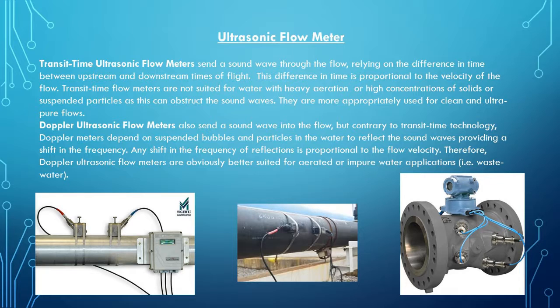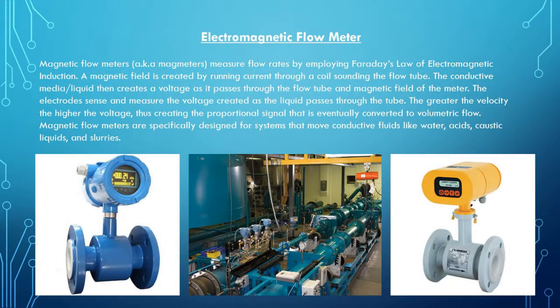Now we will go into more depth on electromagnetic flow meters. Electromagnetic flow meters work on the basis of Faraday's law. A magnetic field is cast across the pipe, and as the liquid moves through the pipe, it is creating a voltage. This voltage is used to calculate the velocity of the liquid inside the pipe.